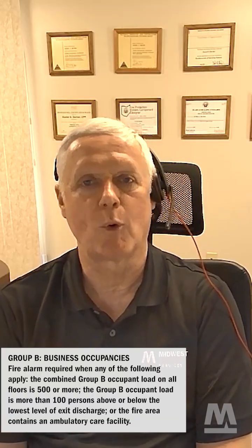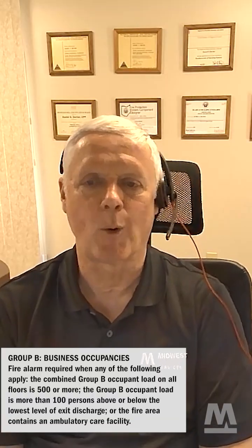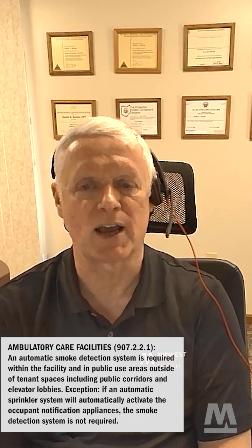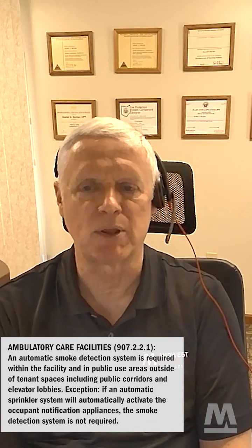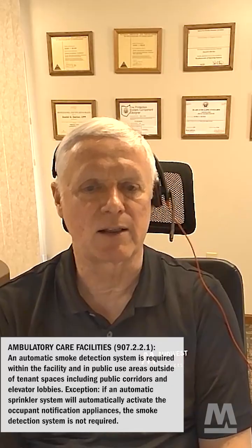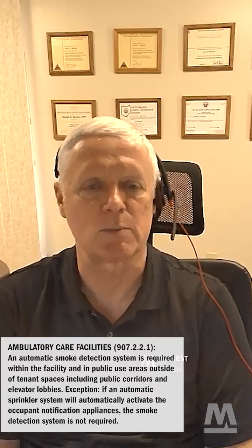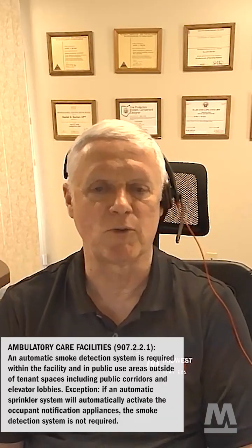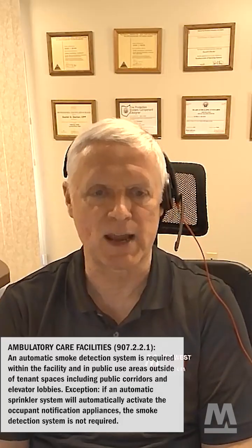Or if you've got an occupant load of more than 100 above or below the lowest level of exit discharge, or if you've got an ambulatory care facility in the Group B occupancy, then a fire alarm system is required. Ambulatory care facilities are kind of a new entrance into the Group B occupancies, and that requires an automatic smoke detection system within the facility and in public use areas outside the tenant spaces that include public corridors and elevator lobbies. The exception to that is if an automatic sprinkler system will automatically activate the occupant notification system, then the smoke detection system is not required.